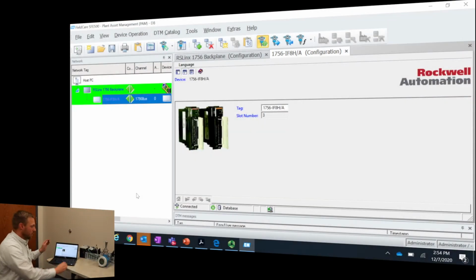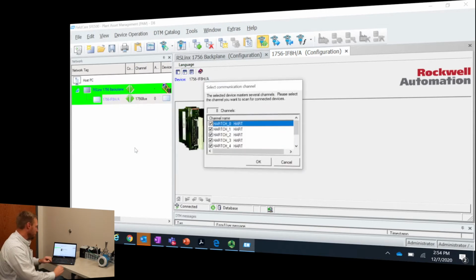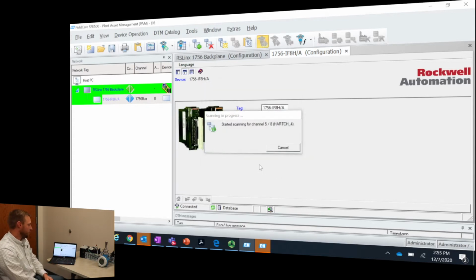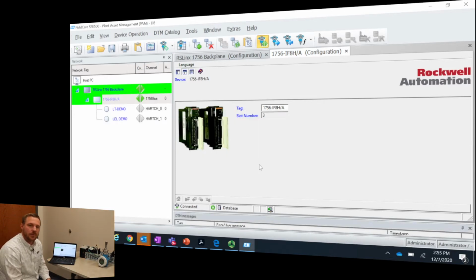All right, so now we are going through the internet, through my laptop, to our network, to our PLC that's on the network, through its backplane, to the card. We're nearly to the instrument now. I'm going to create network. It's asking me what HART channels we want to scan on this card. We'll just scan them all. It should find 2 separate devices. There it is. It's pulling in information for device 1 of 2, and obviously our 2 devices are those. It takes a little while for the devices to pull in.